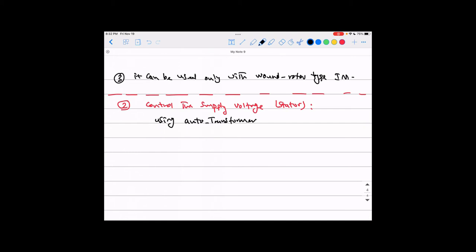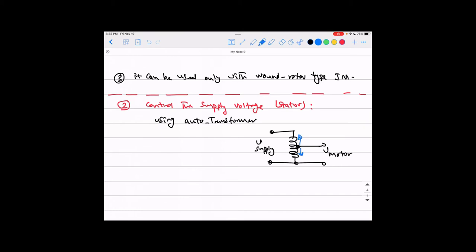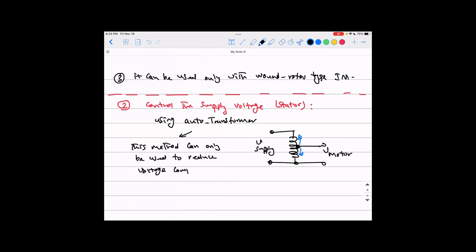We actually have an autotransformer in our lab. The autotransformer has one coil with a moveable tap; you get the voltage from that tap to the motor, and adjusting the tap gives you more or less voltage — so you can control the voltage going to the motor. But before saying anything else, keep this very important point in mind: this method can only be used to reduce voltage compared to the rated value. You cannot increase it above rated — the motor naturally works at rated voltage from the grid.